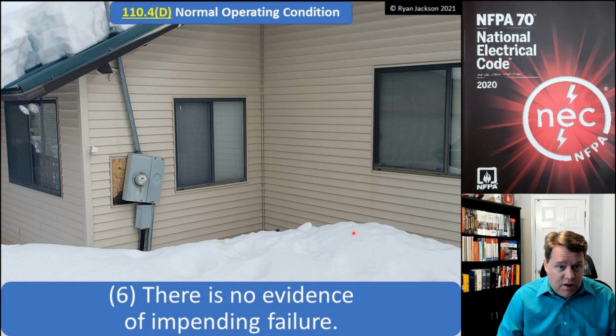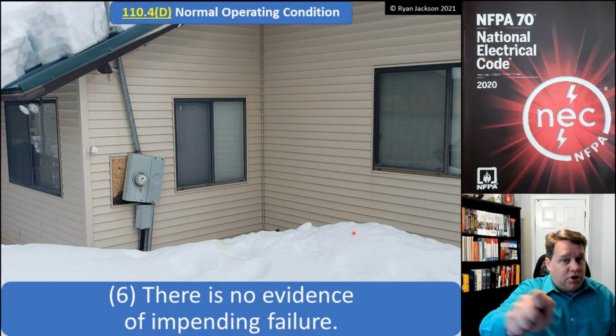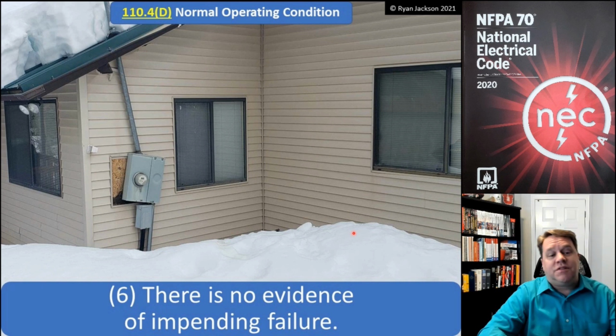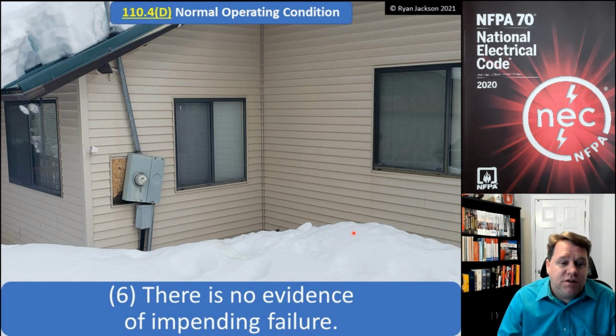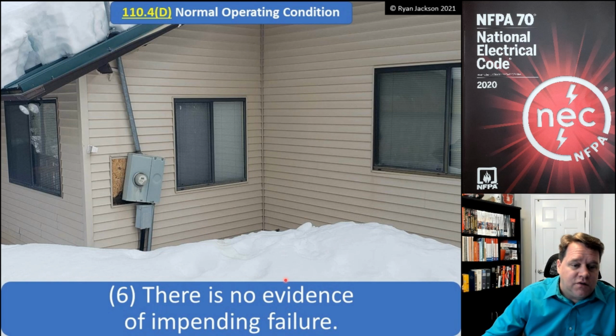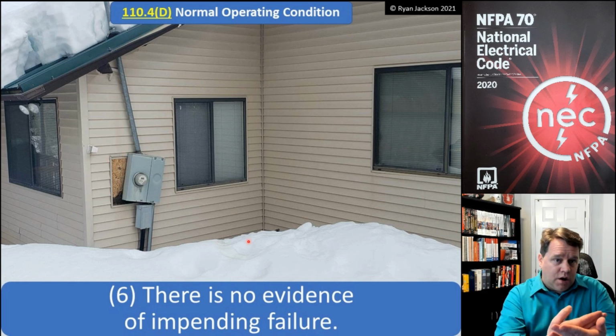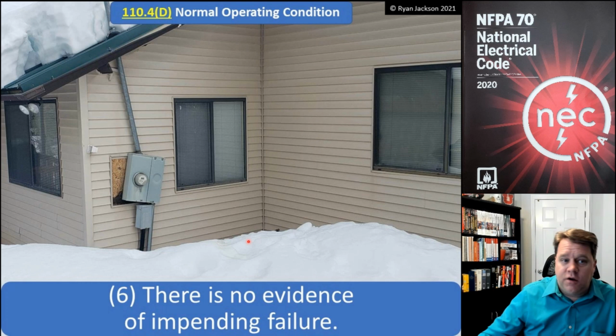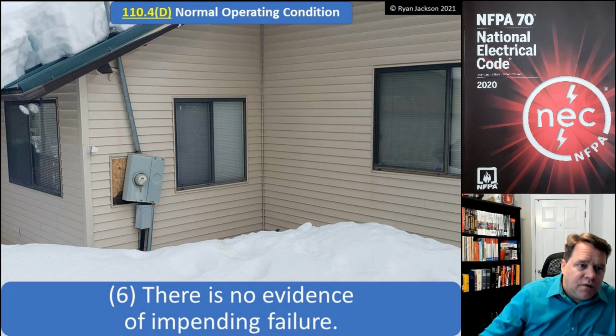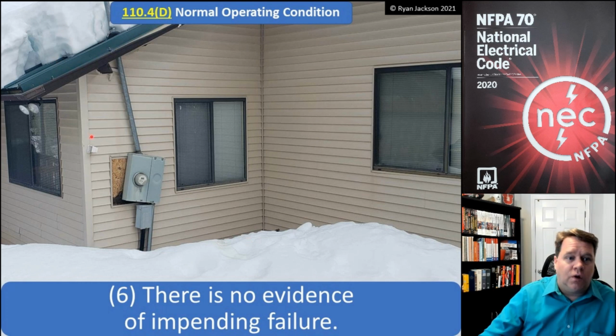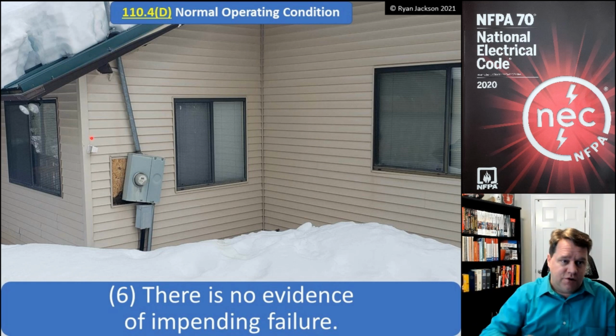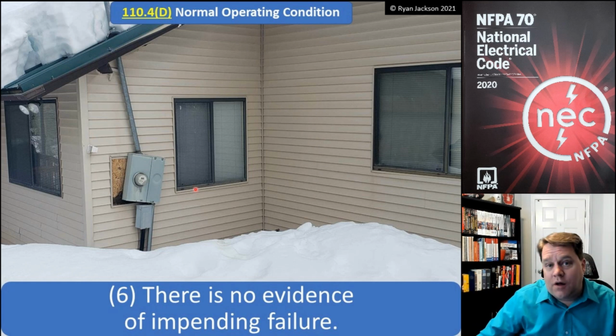Absolutely not. That would be normal operation, right? Turning on and off the breakers, but this is not a normal operating condition. So there is evidence of impending failure. That means it is not a normal operating condition. Think about the screws that held that panel to the wall. They either broke off or they withdrew, right? And you can see if you're not following what happened here, we had like a 3-foot snowstorm and it slid down the roof, knocked the mast right off and ripped the panel off the wall.